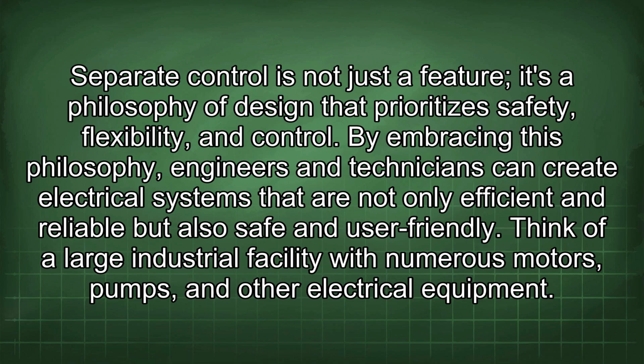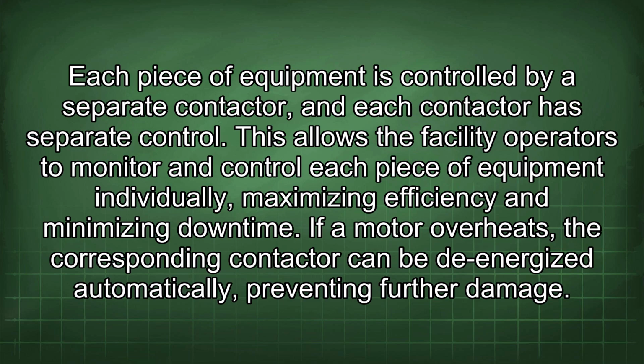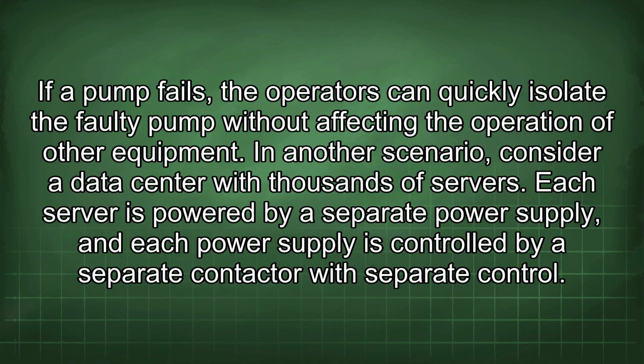Think of a large industrial facility with numerous motors, pumps, and other electrical equipment. Each piece of equipment is controlled by a separate contactor, and each contactor has separate control. This allows the facility operators to monitor and control each piece of equipment individually, maximizing efficiency and minimizing downtime. If a motor overheats, the corresponding contactor can be de-energized automatically, preventing further damage. If a pump fails, the operators can quickly isolate the faulty pump without affecting the operation of other equipment.